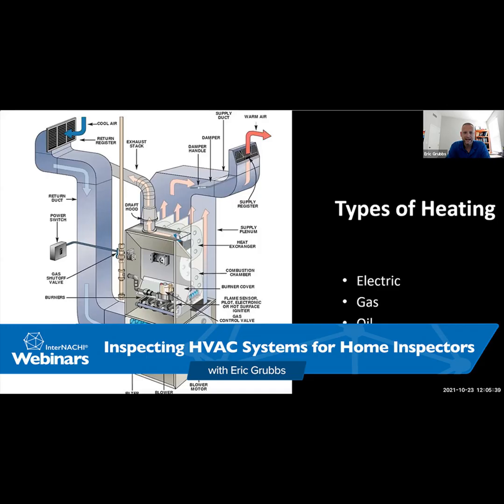Again, our category 4 type, as you can see here, we're using PVC, and you can see where the glue marks are, where it is sealed correctly, so that it doesn't release those positive pressure flue gases into the conditioned space or within the home.